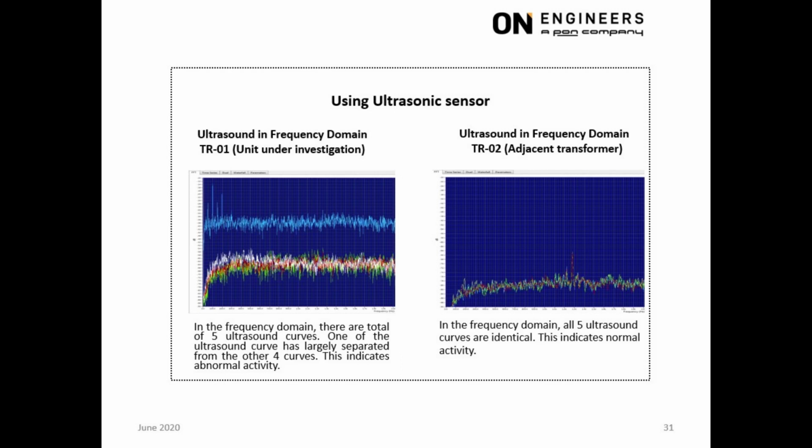There is abnormality. Transformer 2 shows a similar transformer where all 5 ultrasound measurements are identical. This indicates no abnormality.